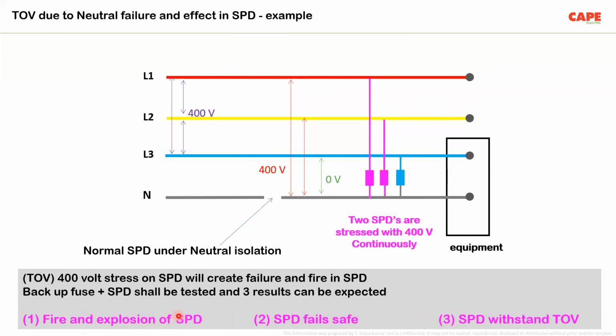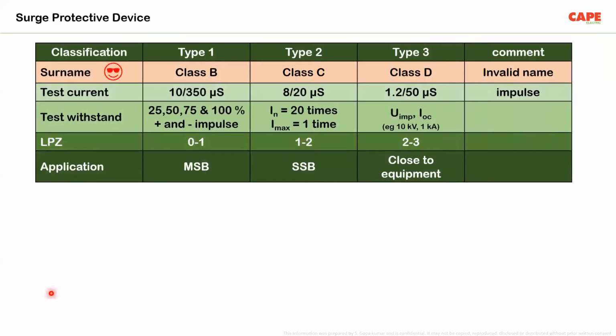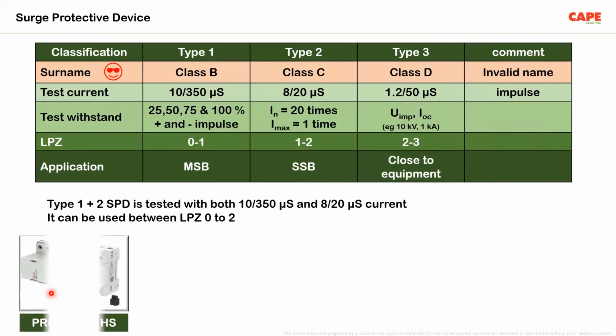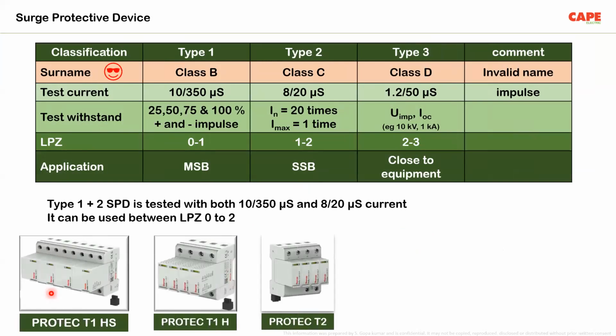Why I am stressing this point more and more is that even today, a lot of SPDs sold and installed are not tested for this parameter, or they fall in the first category. In case of any TOV, of course, you will be in deep trouble. People may ask, what is this SPD? SPDs are surge protective devices. There are three categories for a power line application: type 1, type 2, type 3. These are the SPD categories, but we also have the names class B, class C, and class D. Actually, it's an invalid name. Don't look at it. The correct name is type 1, type 2, type 3.